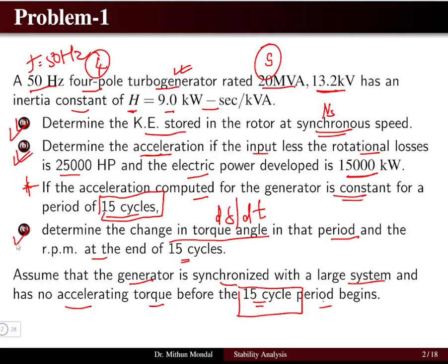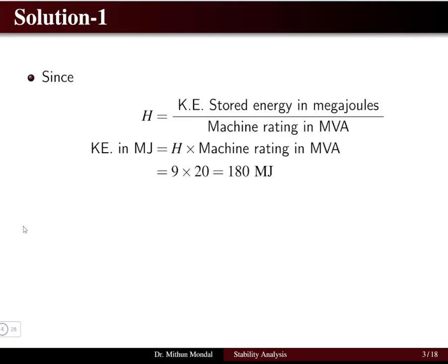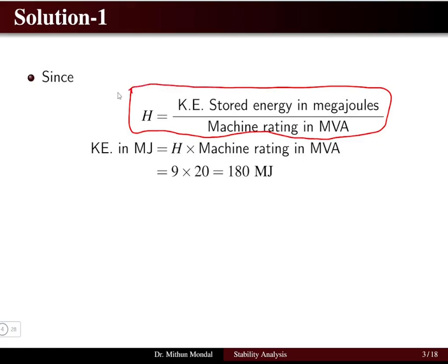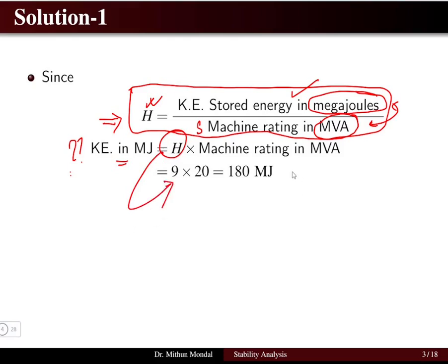Now for the solution. The key equation relating the inertia constant H to kinetic energy is: H = kinetic energy in megajoules divided by machine rating in MVA. Given H = 9 and machine rating = 20 MVA, multiplying the two gives kinetic energy = 180 megajoules stored in the rotor.